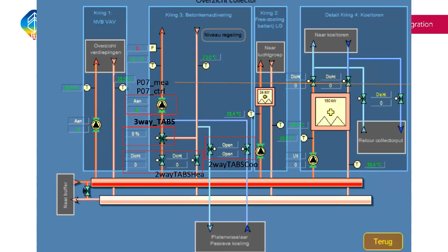So we're controlling these 2 redundant circulation pumps. There are several valves here that allow you to shut down one of the 2 heat pumps, and so we're also controlling these. And what else do we have here? There's a bypass valve here, a pump here. I haven't shown everything yet, but it's just to show that to do such a control, there are quite some things that you need to consider, like redundant pumps, shut-off valves, etc. So these are all things that we have to take into account.